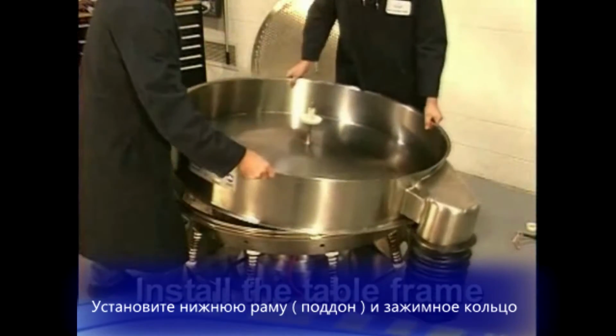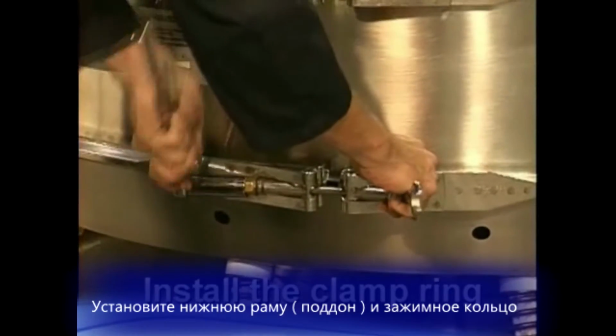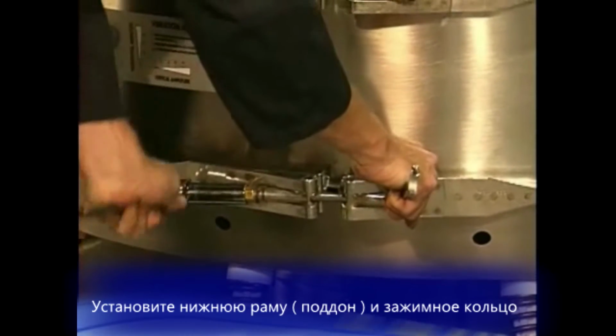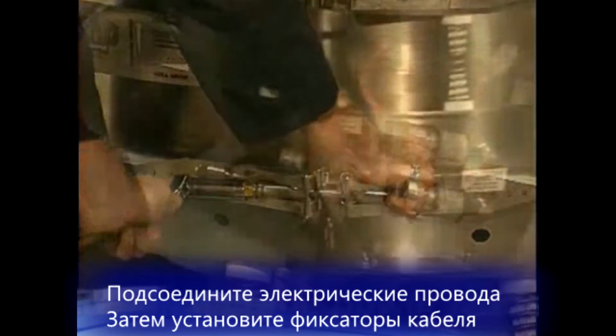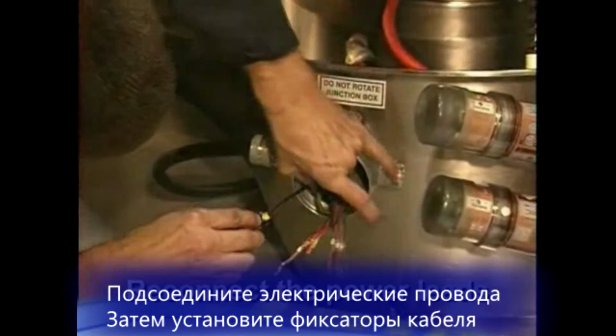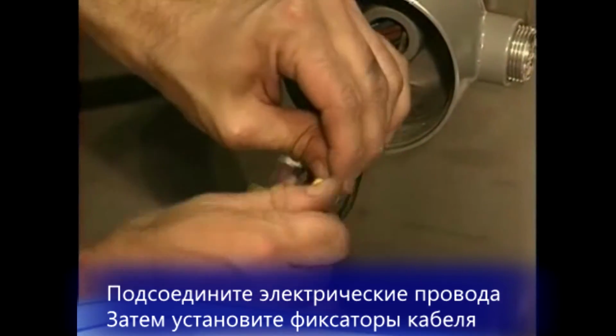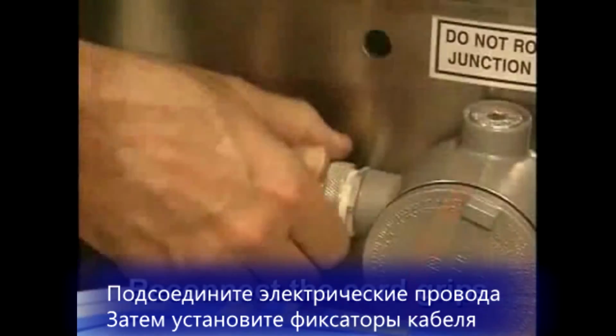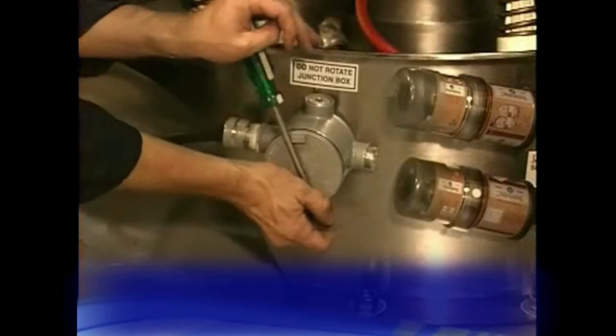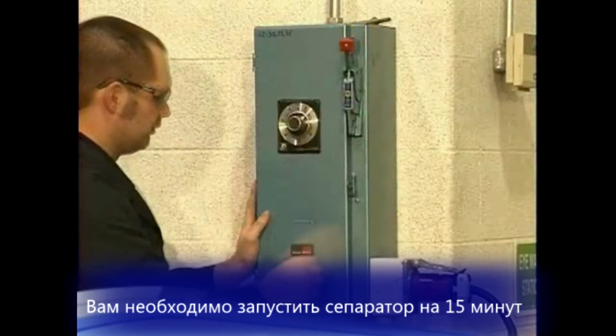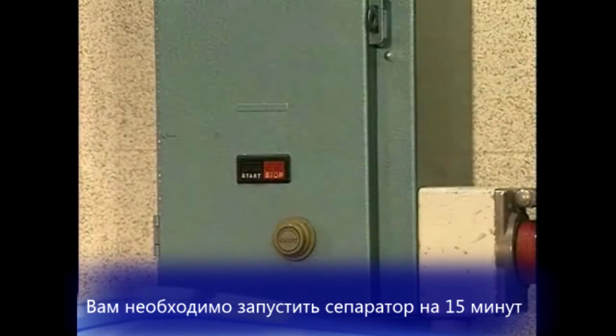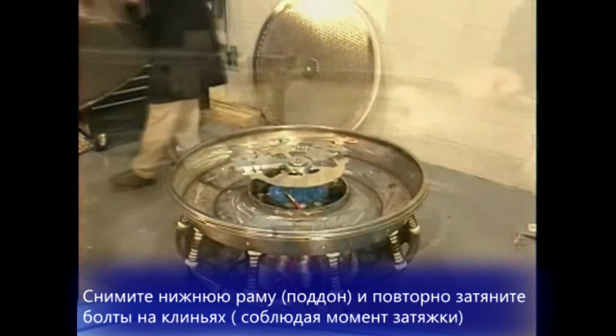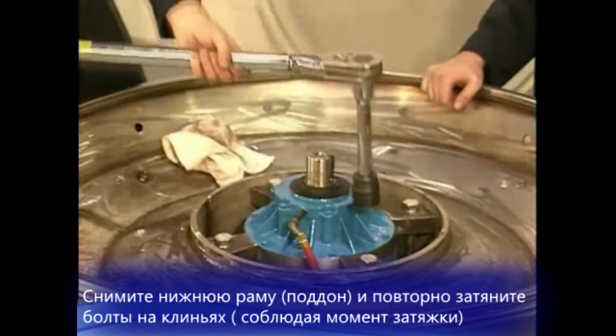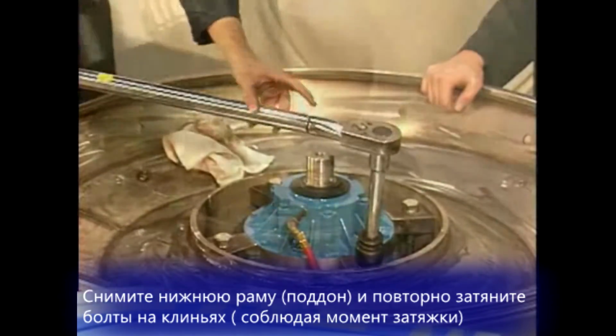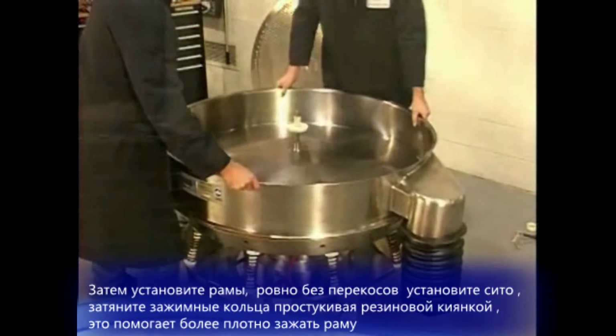Install the table frame and clamp ring. Reconnect the power leads, and then the cord grips. You will need to run the separator for 15 minutes. Remove the table frame and re-torque the wedge bolts. Then reinstall the frame stack with the screens.